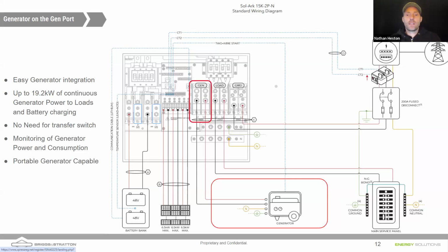Now I'm showing a similar wiring diagram, but we're using the generator port to bring in a generator. And you can see there's a two-wire signal to start connection that comes out of the accessories bar on the communications on the Sol-Ark 15K. What that will do is, if we have a grid down situation, it will not automatically start up the generator as we're used to with transfer switches, right? What happens if you have a grid down situation is that the batteries will be backing up the home, and the generator doesn't start up until the batteries get low enough that they call for the generator to start up and cover loads and run a charge cycle on the batteries. And that's done with a two-wire signal to start. We'll get into how to program for that and what your options are for that as well.